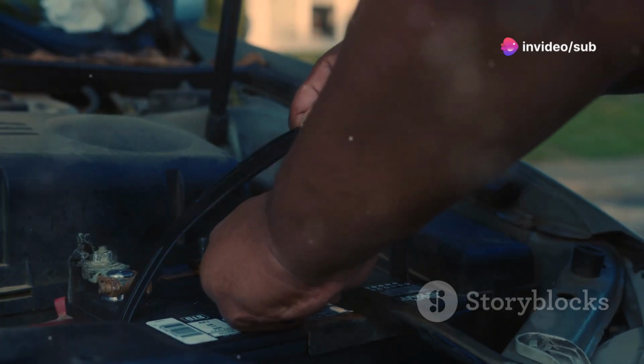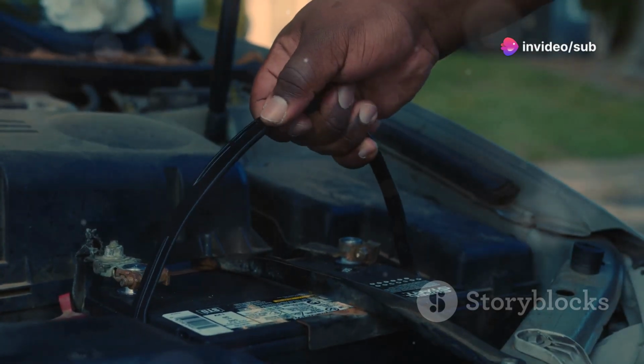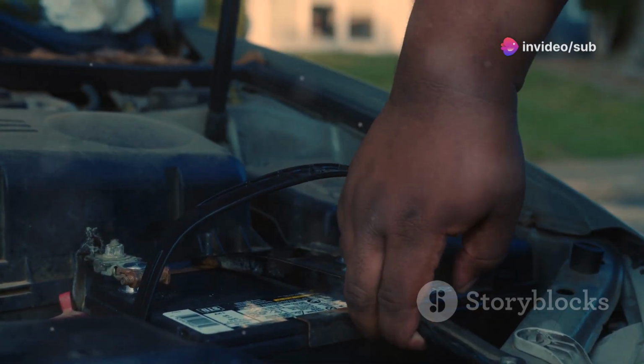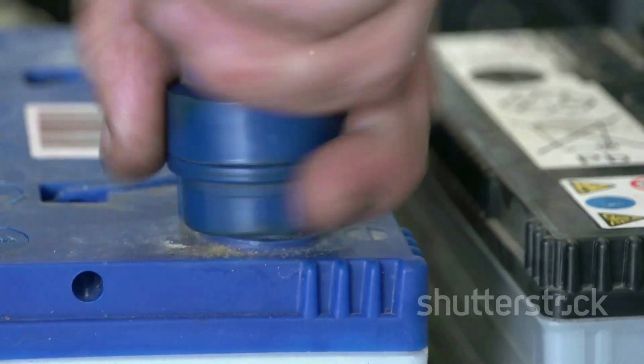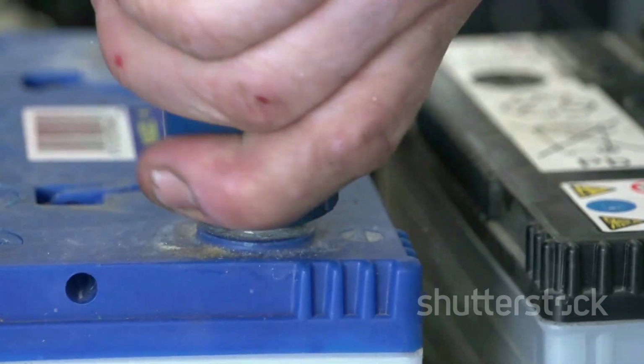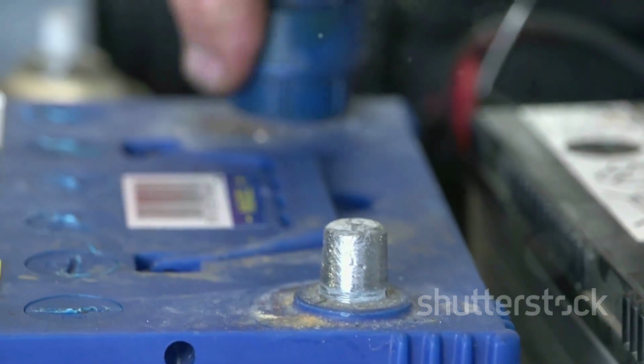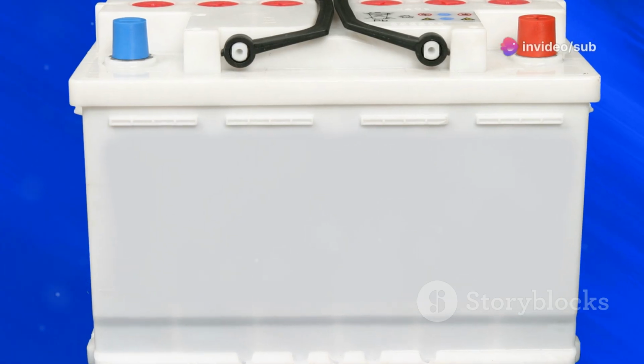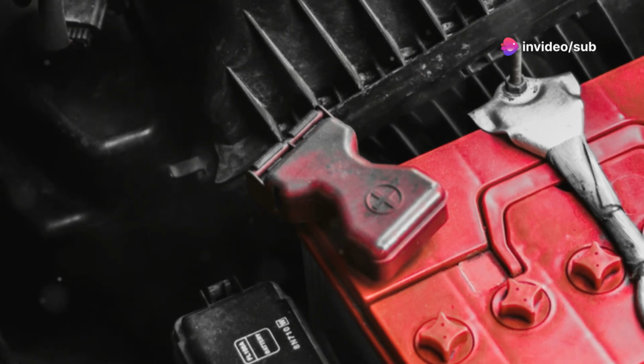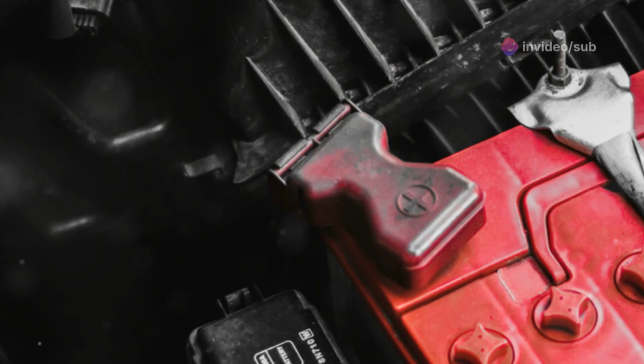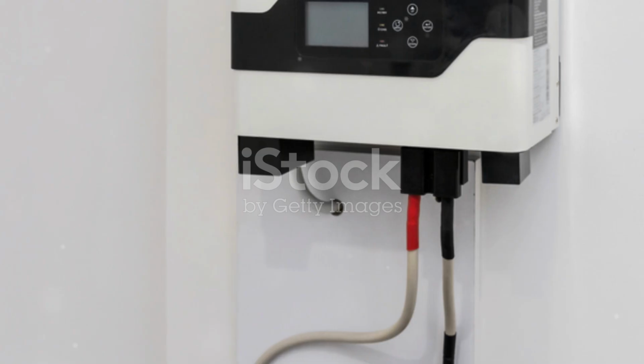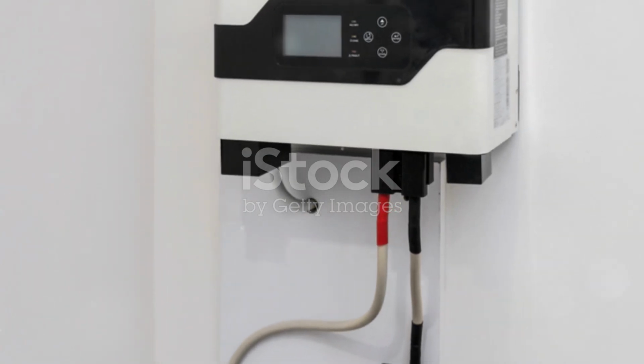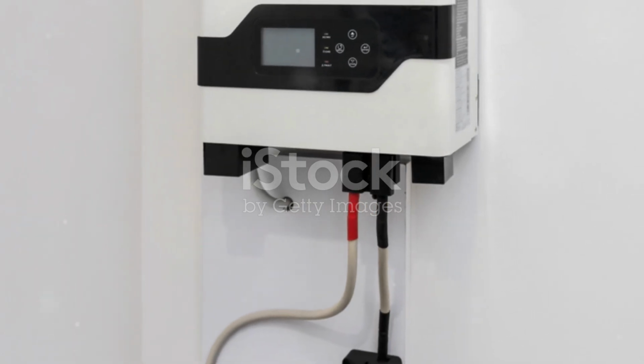After connecting everything, tighten all the terminal connections securely with a wrench. Loose connections can cause sparks, heat buildup, or even system failure, so double check for any loose wires or signs of arcing before moving on. Once your connections are secure, cover all battery terminals with plastic caps or insulation to prevent accidental contact. It's also a good idea to label each cable clearly. This makes future maintenance safer and much easier to manage.